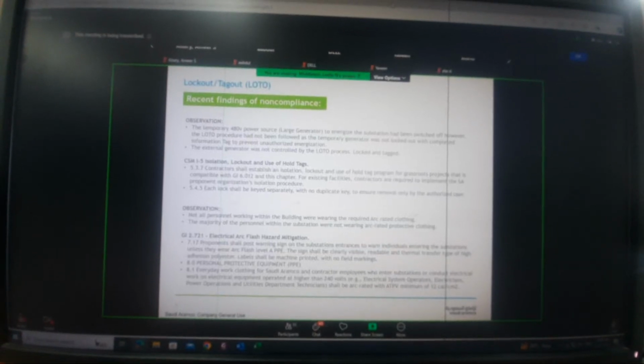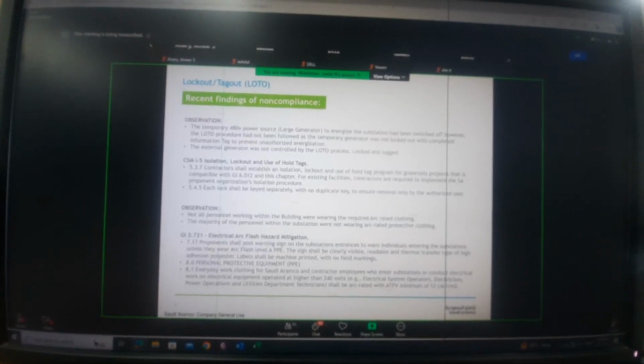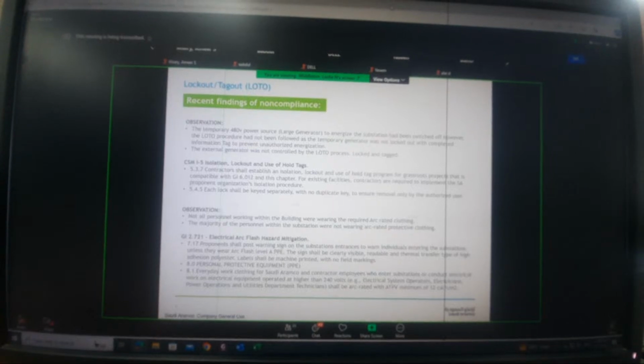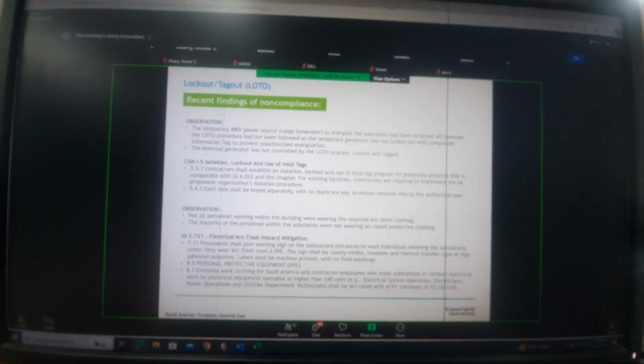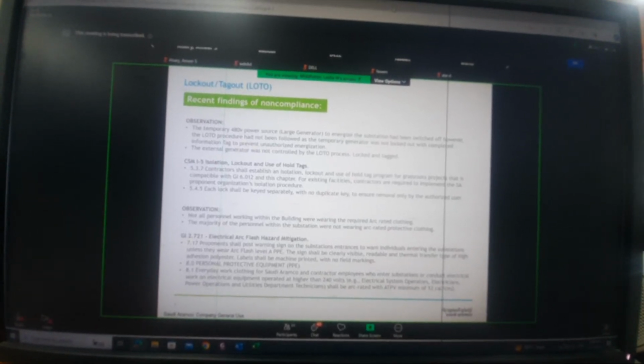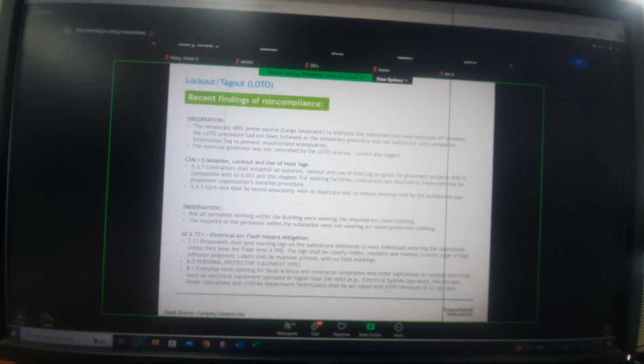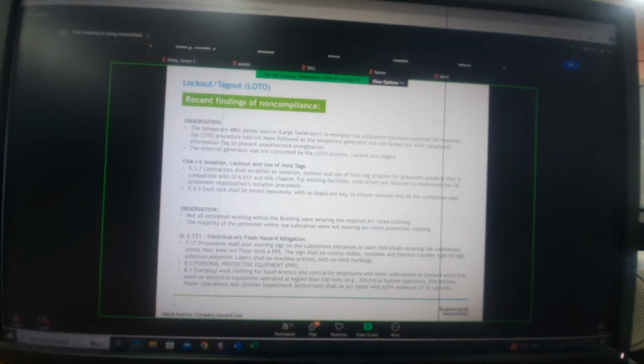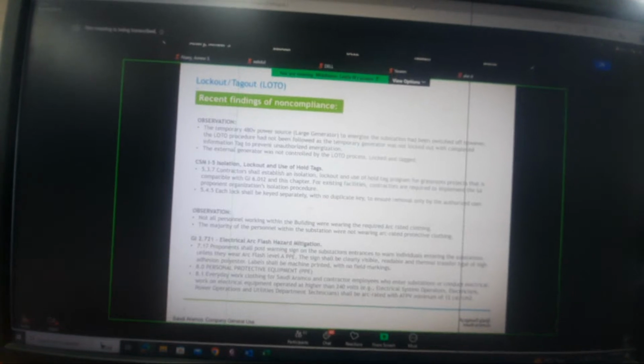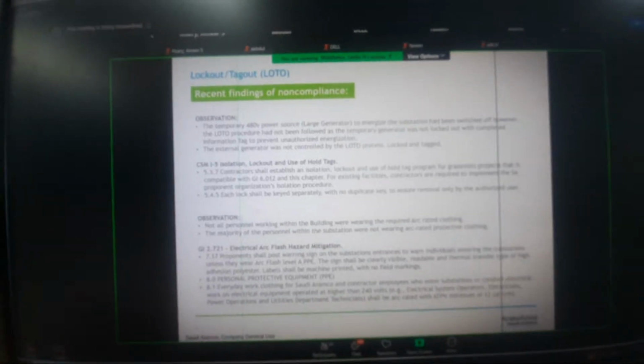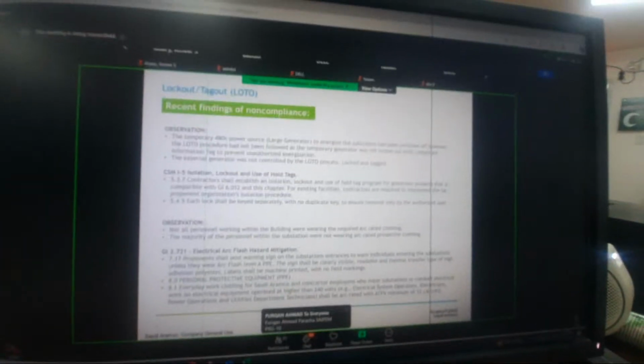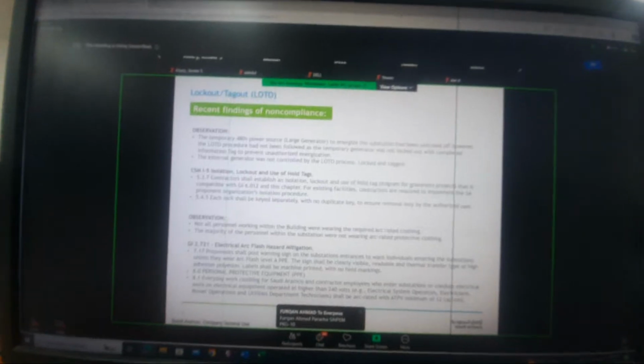There is no difference between permanent and temporary power, and this again isn't spelled out anywhere in any of the GIs. It basically talks about the voltage being used during the operations. So when you think of a temporary generator out on site for a substation, that's no different than having your main supply power. So we should be controlling that the same.